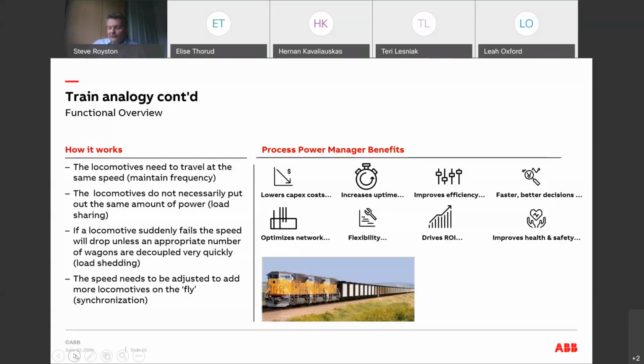In power management system solutions, we perform this load shedding extremely quickly using digital outputs hardwired to the trip relays on the circuit breakers, or by sending commands to the protection relay using an Ethernet protocol called IEC 61850, which can transmit the load shed command in a matter of milliseconds.